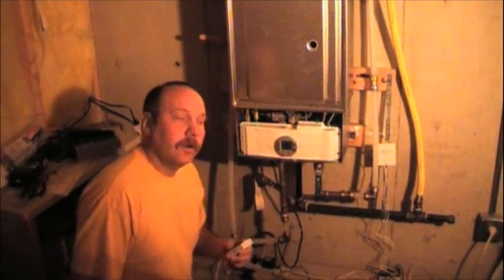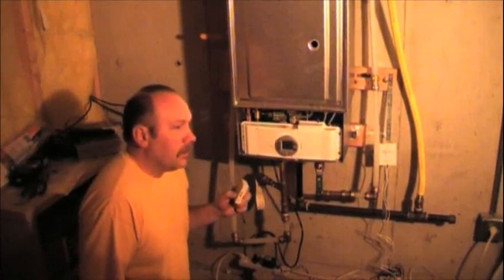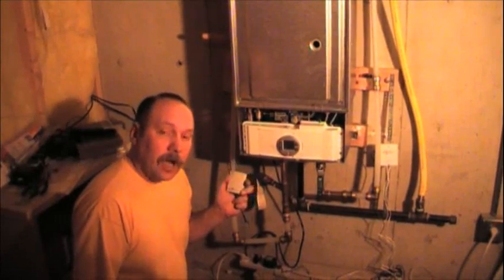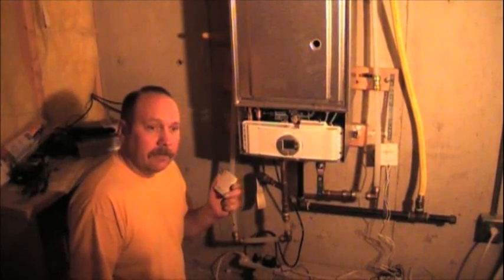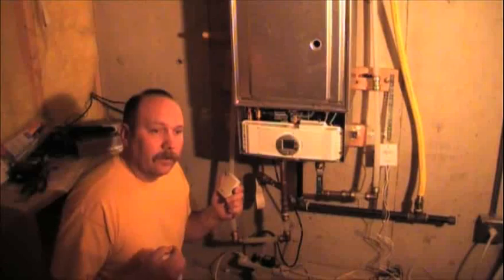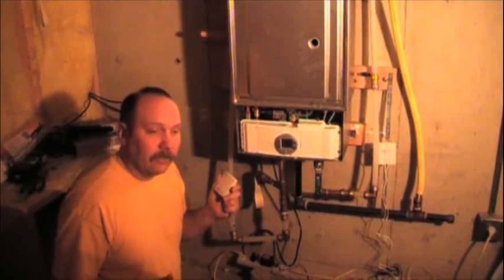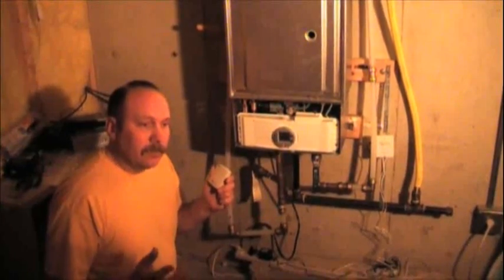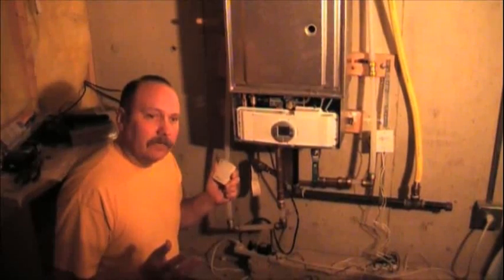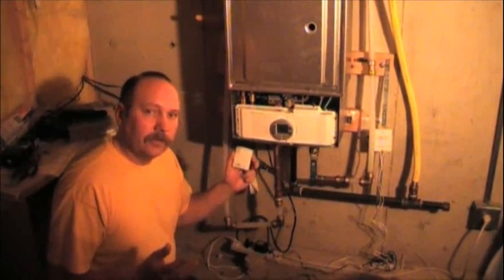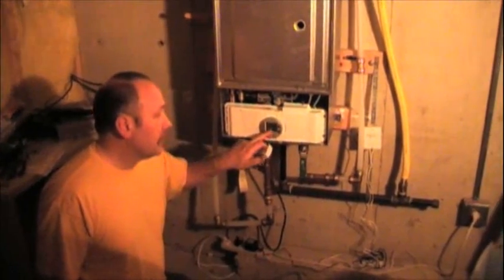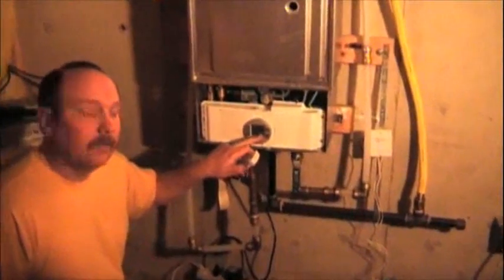Okay, we're now at the tankless water heater. One of the most common complaints is that people have not enough hot water, or it's not hot enough at the shower head. So what we need to do is look and see if the unit itself is actually performing to what we have asked it to. This particular tankless water heater is sitting at a requested temperature of 122 degrees.